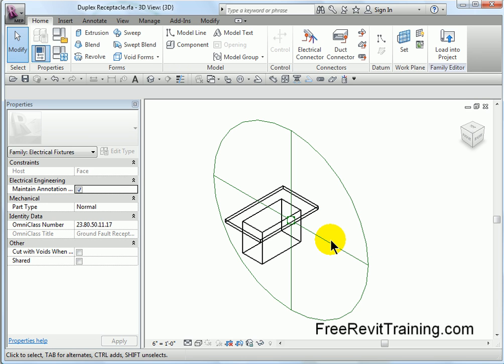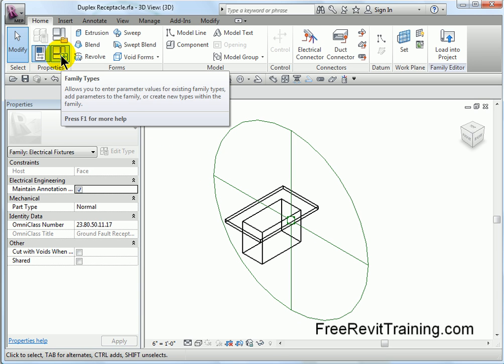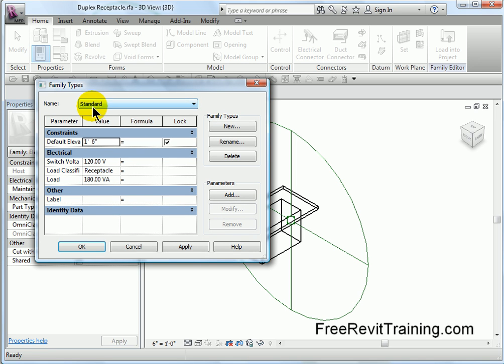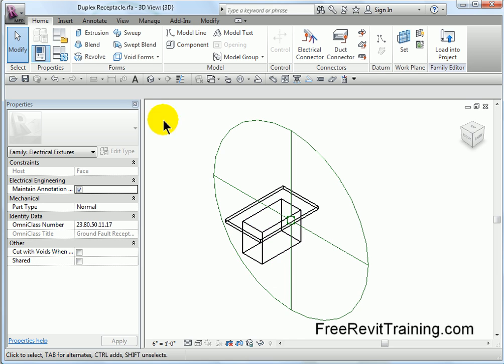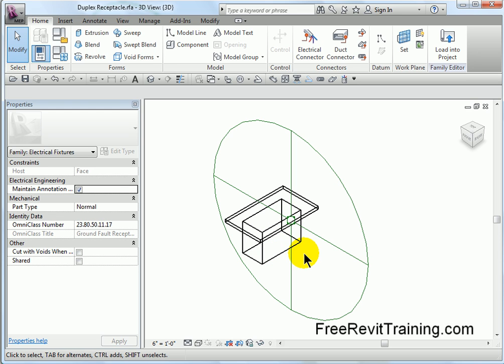At this point, everything looks good, but we started to notice some things about this receptacle. If we go up to the properties box and look at family types, you'll notice the only option set is the default elevation. There's no other settings. If I drop this down, there's a GFI option, which just adds a label — but notice there's no sizes, no adjustability whatsoever. Let's say we need to change the box size. Maybe we're doing conduit and need a 4x4 box, maybe even a special depth. We're going to come in here and adjust the box size and build in parameters. We'll also add conduit connectors so it's easy to run conduit off this box — currently not so easy.